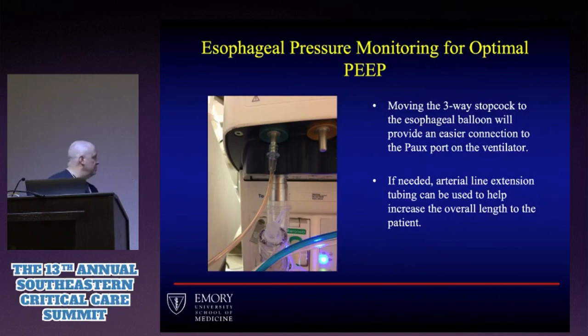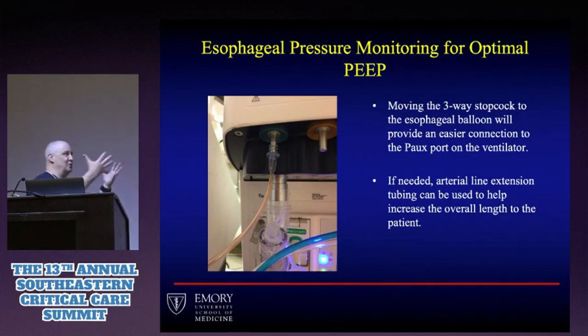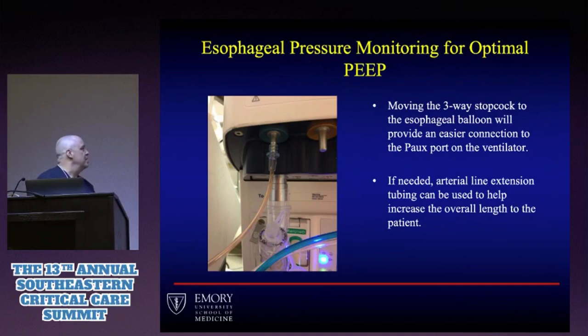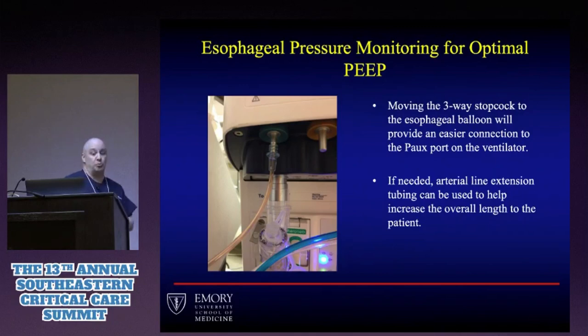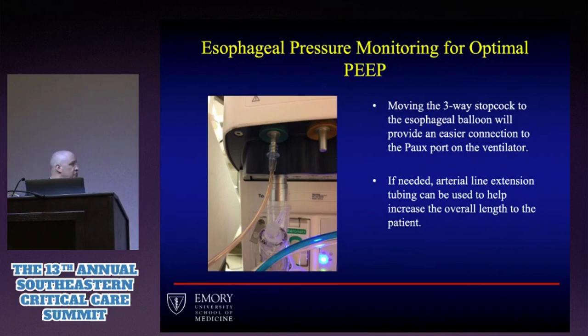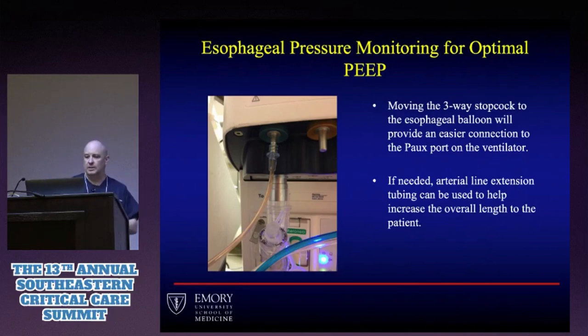Hooking it to the machine is very simple — it's a direct connection to the ventilator, and you access the ventilator to get your pressure measurements, which are mathematically calculated for you. If the machine is far from the patient, you can use art line tubing for extra length from the catheter to your ventilator to minimize any pressure dampening.